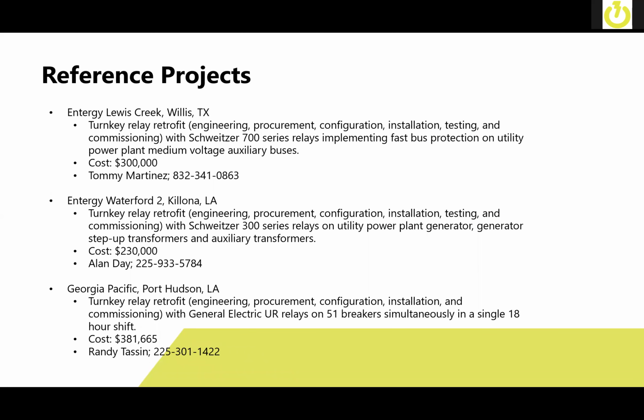Some reference projects that we've worked on. We've done some jobs for Entergy over at Lewis Creek in Willis, Texas. This one in particular was a turnkey relay retrofit, included all engineering, all procurement, all configuration, installation, testing, power system studies, etc., with Schweitzer 700 series relays. We also implemented a fast bus protection scheme on the power plant medium voltage auxiliary buses that drastically reduced their arc flash incident energy. Cost was approximately $300,000 for that.